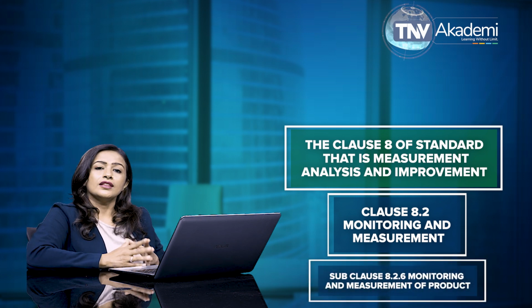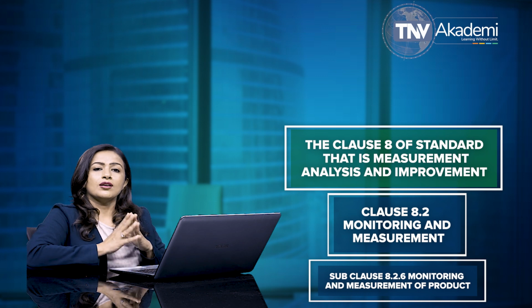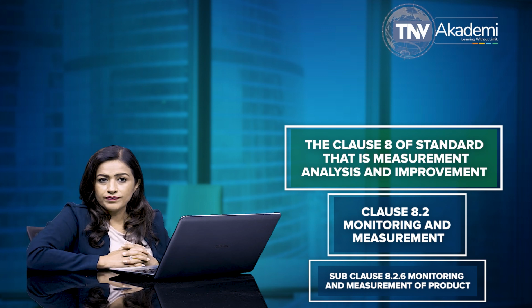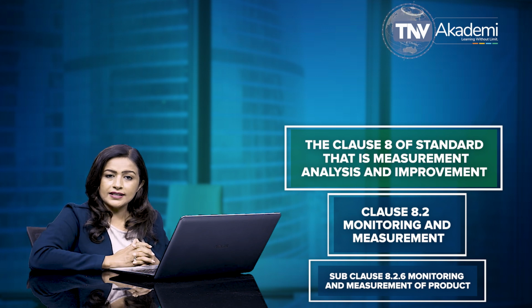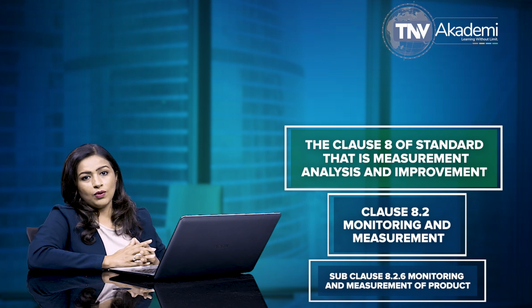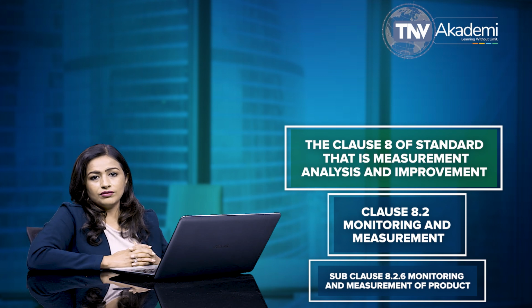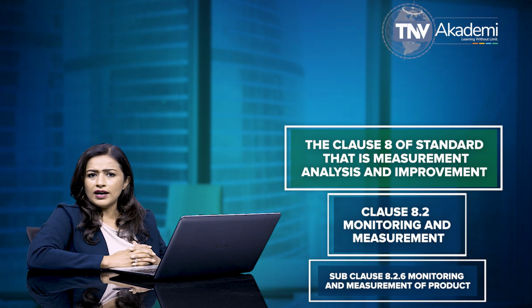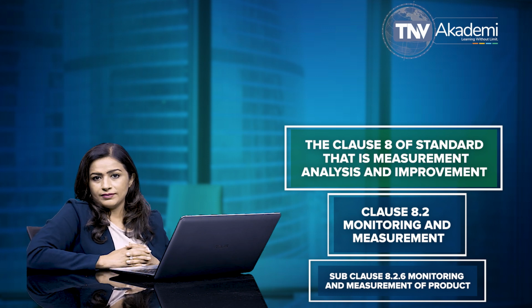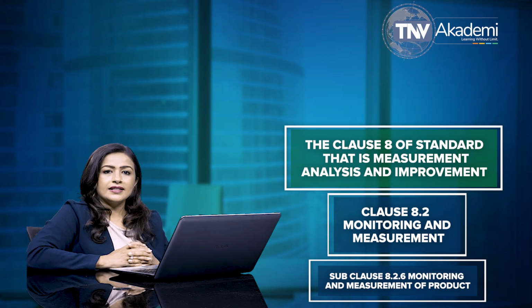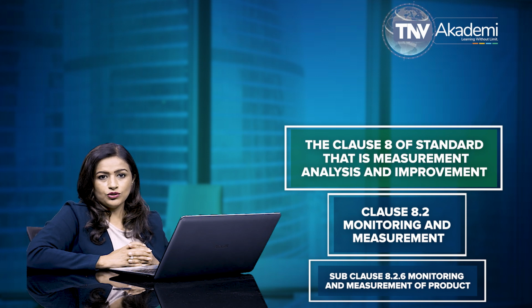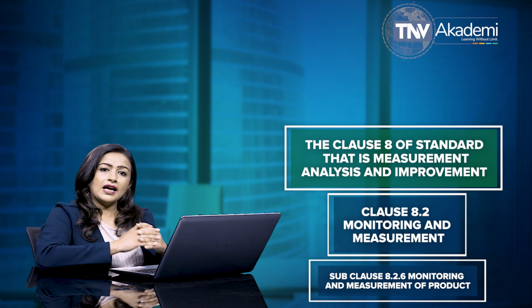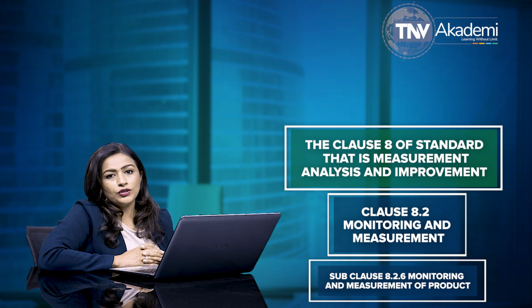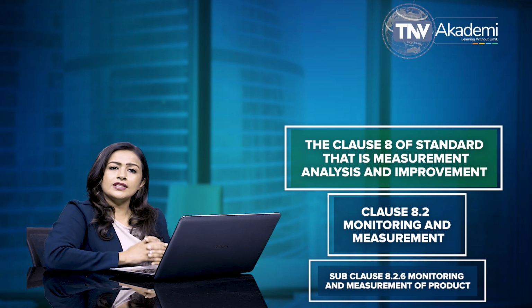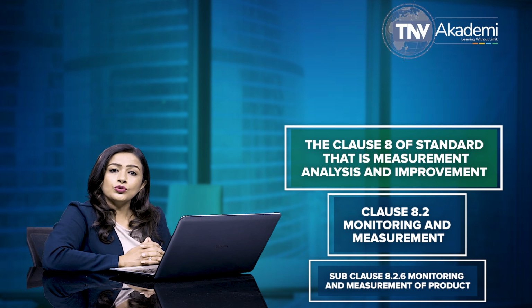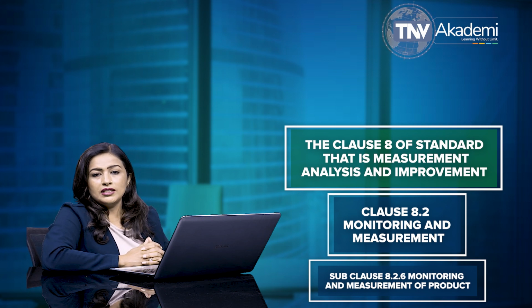Let us now discuss the subclause 8.2.6, monitoring and measurement of product. The subclause 8.2.6 specifies that the organization is required to monitor and measure the characteristics of the product to verify that product requirements have been met. This must be carried out at applicable stages of the product realization process in accordance with the planned and documented arrangements and documented procedures.